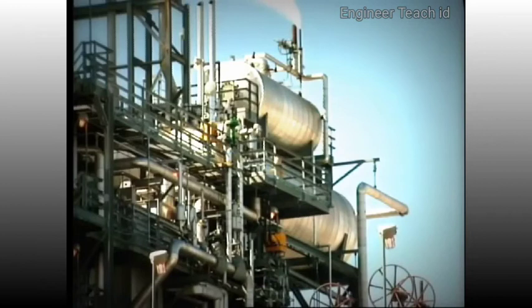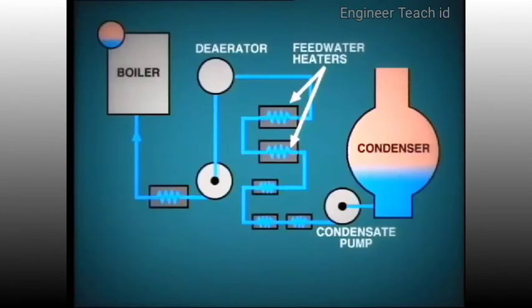Often, the de-aerator is located at a high elevation in order to provide a positive pressure to the suction of the boiler feedwater pump. The boiler feedwater pump draws condensate from the de-aerator and pumps this through further closed feedwater heaters, one in this example, and on into the boiler.